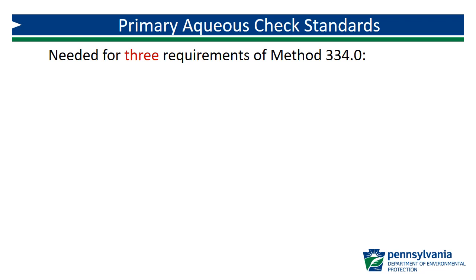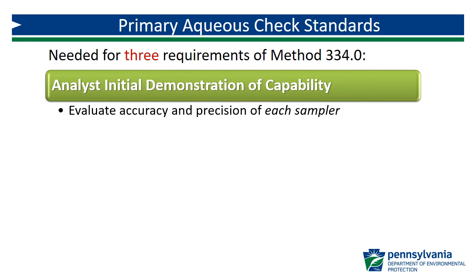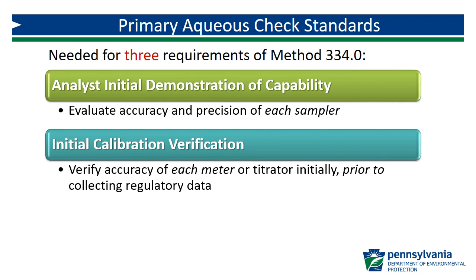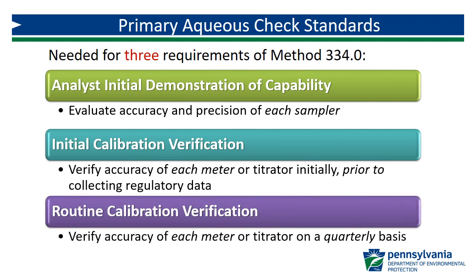Primary aqueous standards are needed for three different requirements of Method 334.0. First is the analyst initial demonstration of capability, used to evaluate the accuracy and precision of each individual sampler analyzing grab samples for compliance or comparative grab sampling. Second is the initial calibration verification for grab sample equipment, which verifies the accuracy of each meter or titrator. Third is routine calibration verification for ongoing verification of meter or titrator accuracy. Each of these will be covered in much greater detail in subsequent videos.